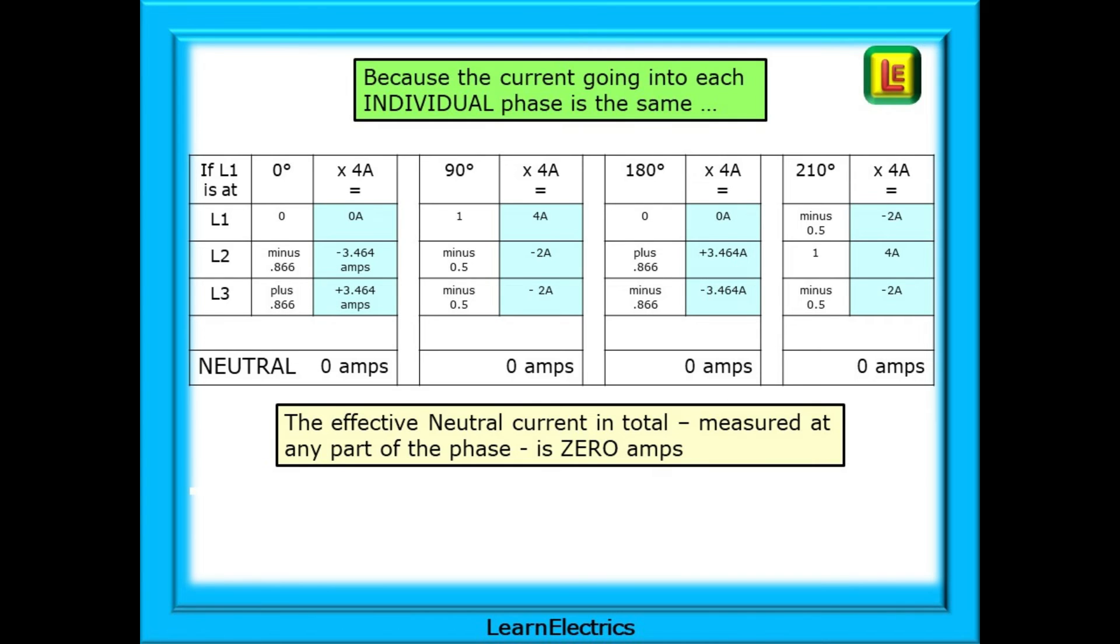Different numbers at 180 degrees, but still 0 amps. And then, at 210 degrees, different values again, but mathematically, all at 0. Because we are using the same size heater, 4 amps, on every phase, the circuit is balanced. The effective neutral current, in total, measured at any part of the phase, is 0 amps.